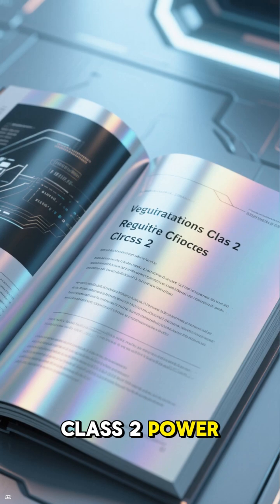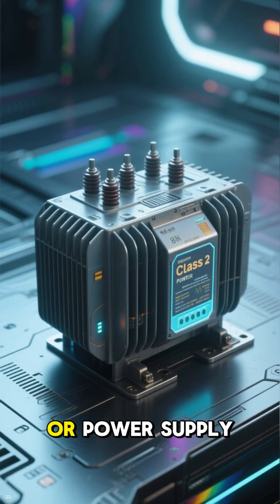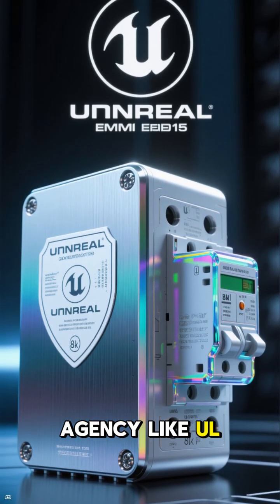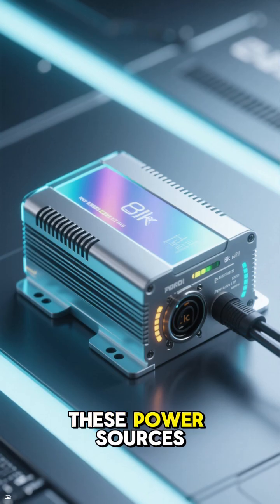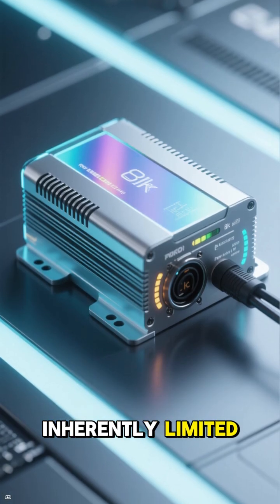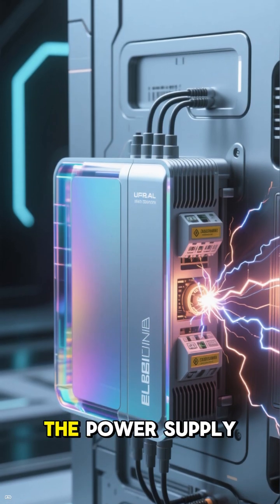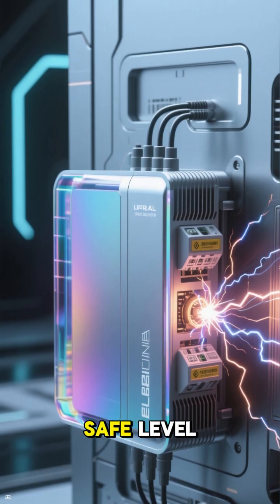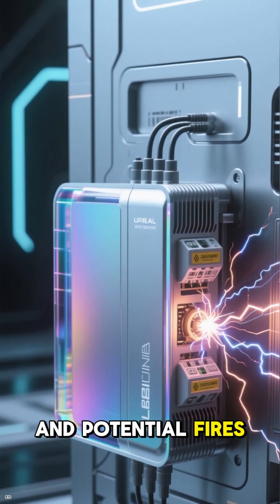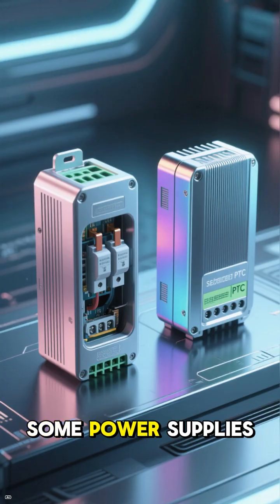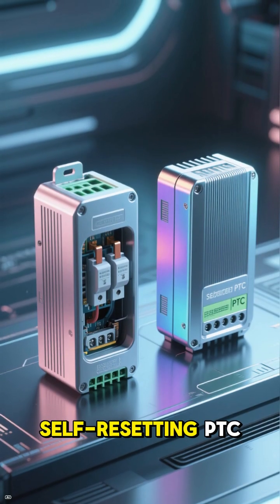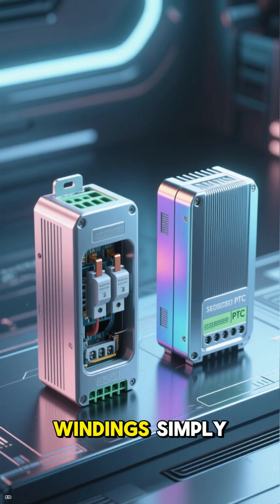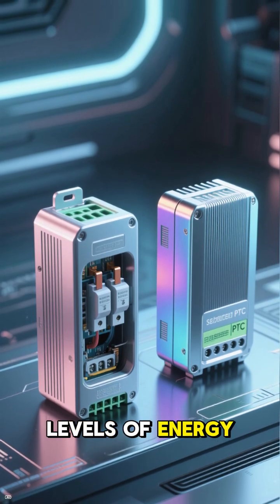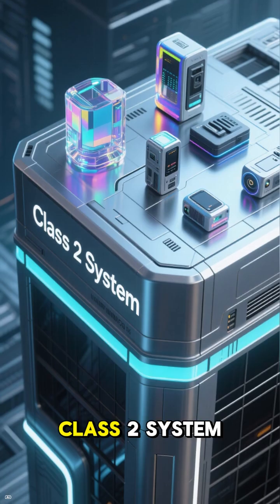A crucial requirement is that a Class 2 circuit must be fed by a listed Class 2 power source. This isn't just any old transformer or power supply. It has to be a device that has been tested and certified by a recognized agency like UL to meet the strict energy limiting requirements. These power sources are designed to be inherently limited. This means that even under a short circuit condition, the power supply will automatically limit its output to a safe level, preventing overheating and potential fires. It's a built-in safety feature. Some power supplies achieve this with an internal fuse or a self-resetting PTC, while others are designed so that their windings simply can't produce dangerous levels of energy. This inherent protection is the bedrock of the entire Class 2 system.